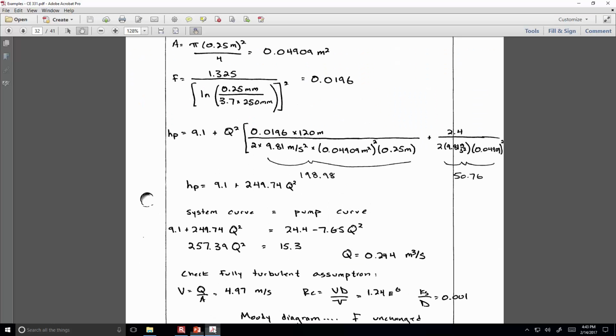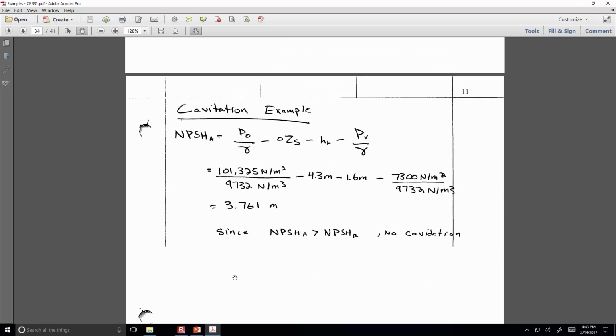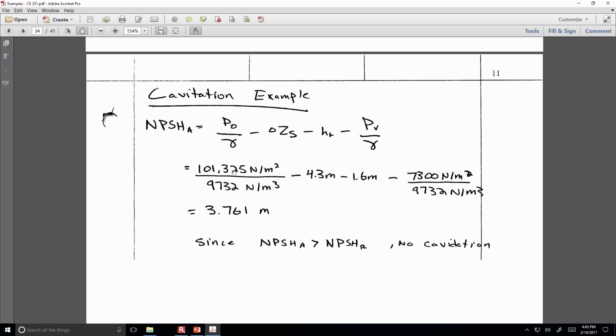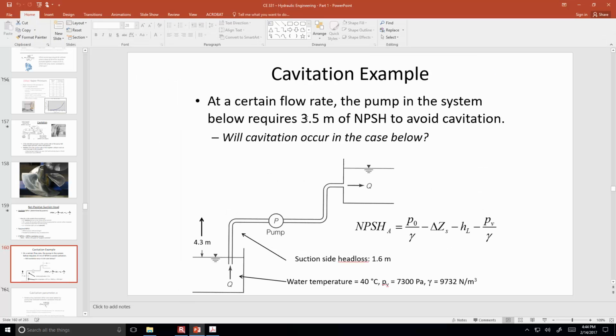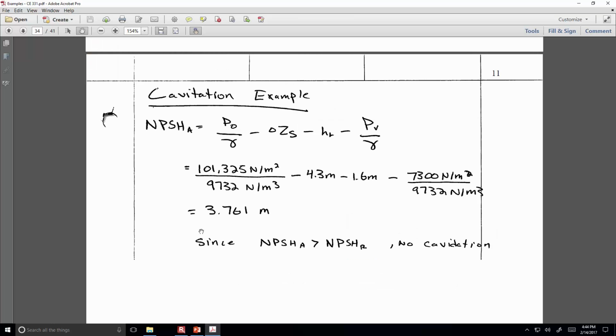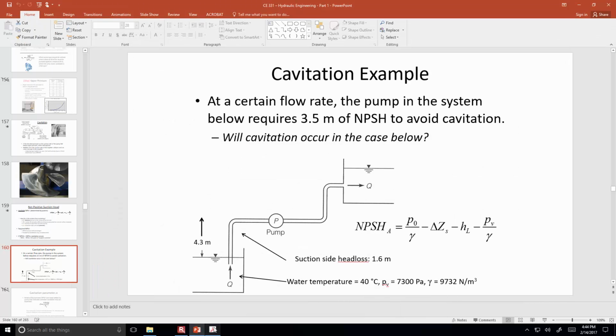So we take a look at how much is available and how much is required. Here's the atmospheric pressure in absolute terms. That's our first term, and all the others are going to reduce how much head is available. In the end, it has 3.7 meters of head available, and the required amount from the problem statement is 3.5. So under these conditions, there's not going to be any cavitation. But all we'd have to do to get cavitation is lift this pump an additional 20 centimeters higher, and then it's going to start having cavitation, and the impeller is going to start getting eroded. It would sound bad. It's an altogether dangerous situation you want to avoid. We're pretty close right now to having cavitation.